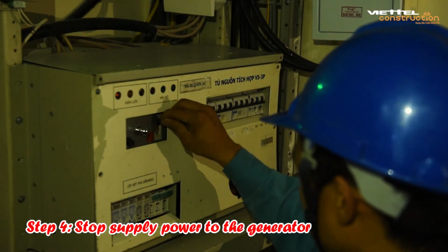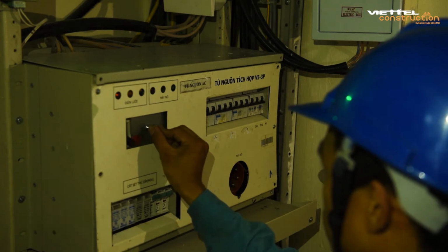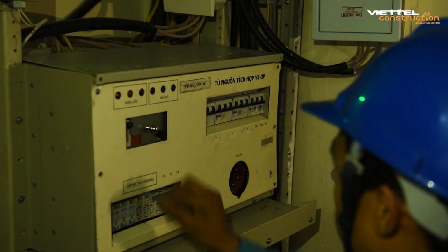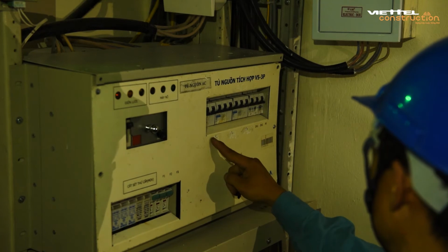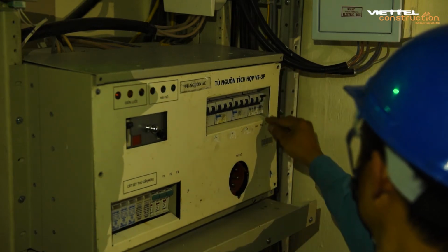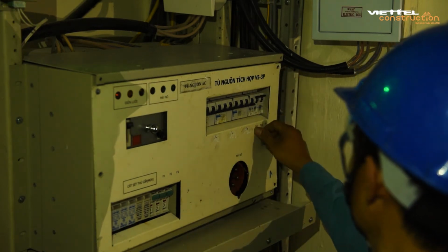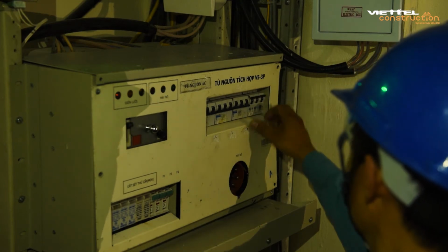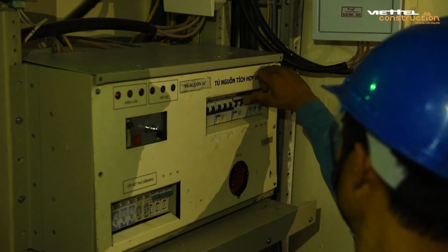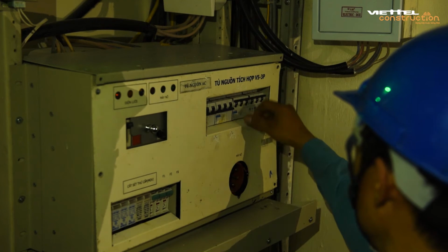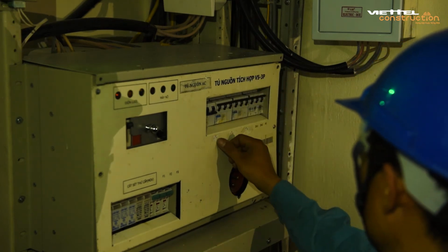Step 4. Stop supply power to the generator. After checking the parameters and operational status of the machine has met the requirements, then proceed to close the load in order from large to small. When the generator has enough capacity to supply power to the station, it is not allowed to cut down on auxiliary equipment such as ventilation and air conditioner.